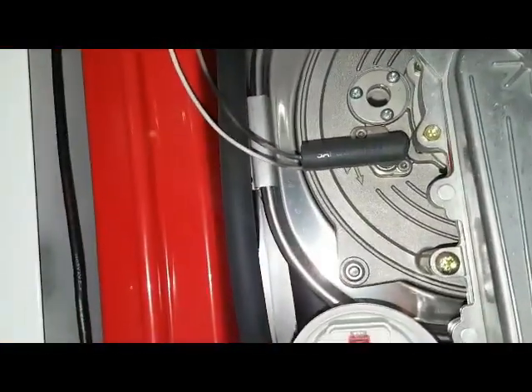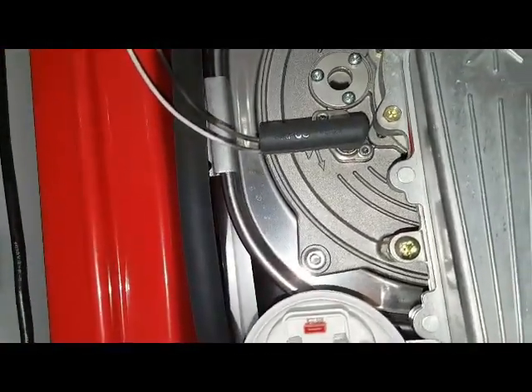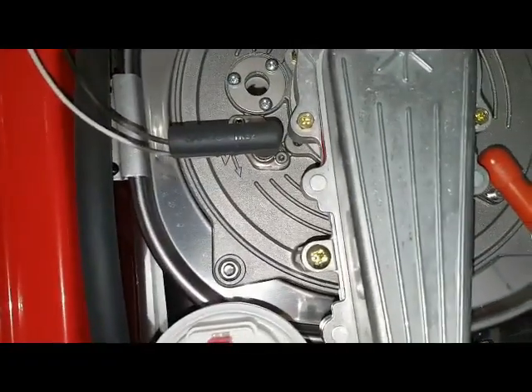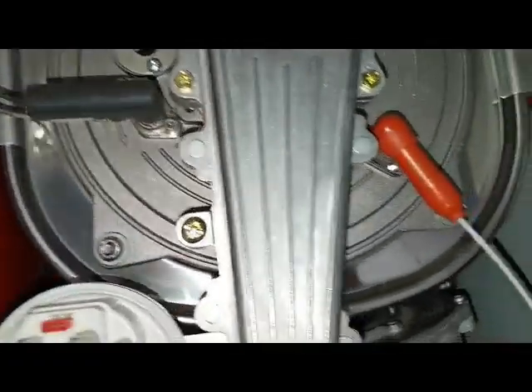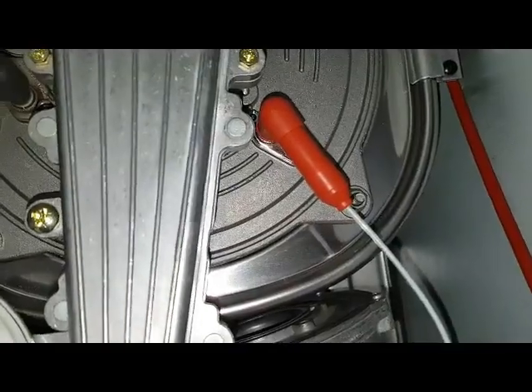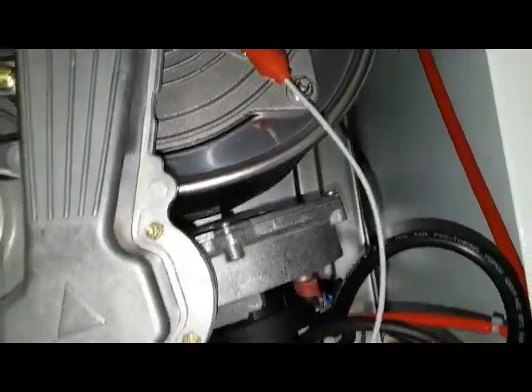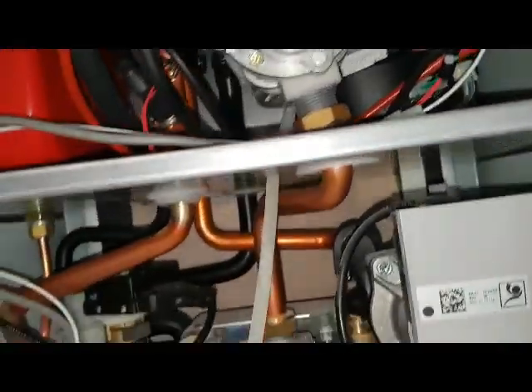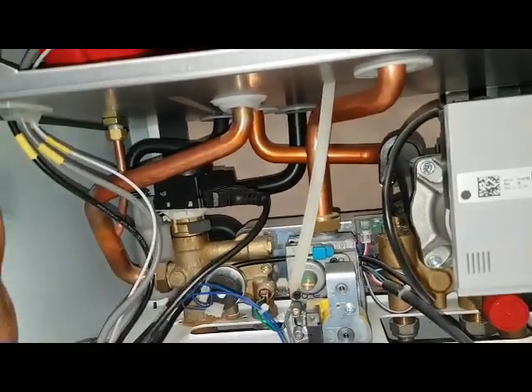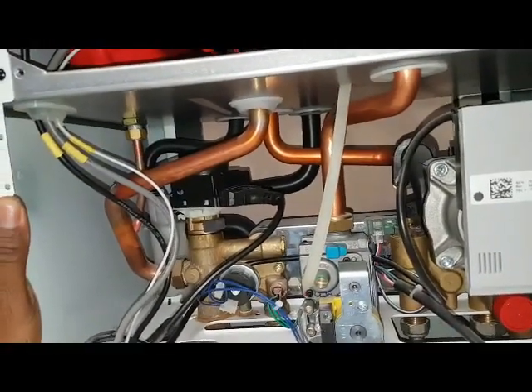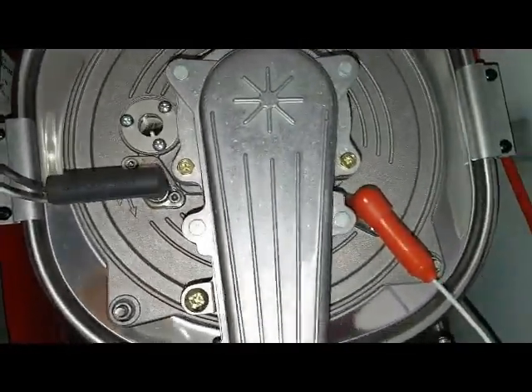Then you're going to get a spark. Spark lights the gas, ignites it. Flame detection sees the flame, okay. Sends a signal down to the board to keep the ignition sequence going and the combustion. So then it's combustion burning.